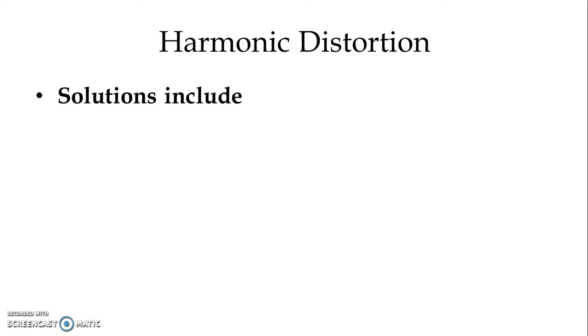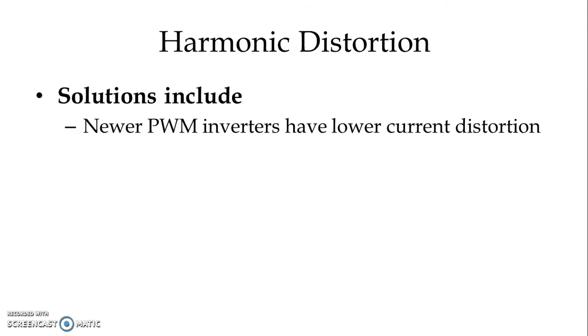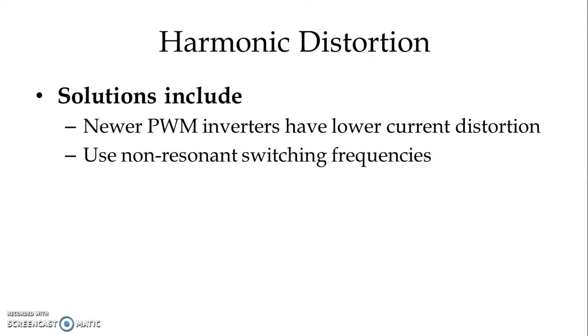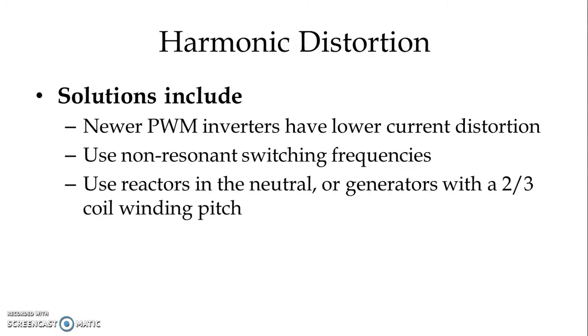Some solutions include newer pulse-width modulated inverters that have lower current distortion, using non-resonant switching frequencies, and using reactors in the neutral or generators with two-thirds coil winding pitch.